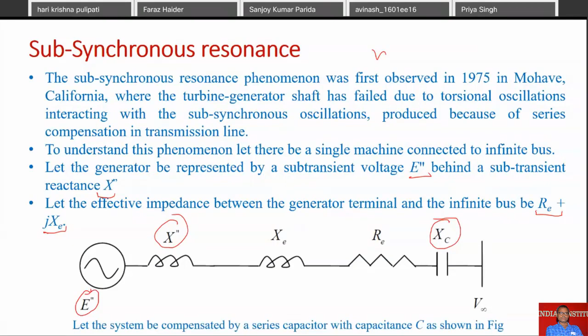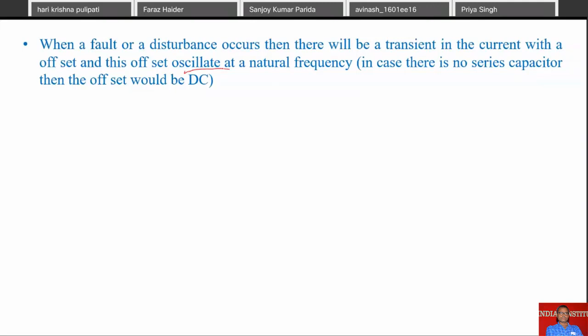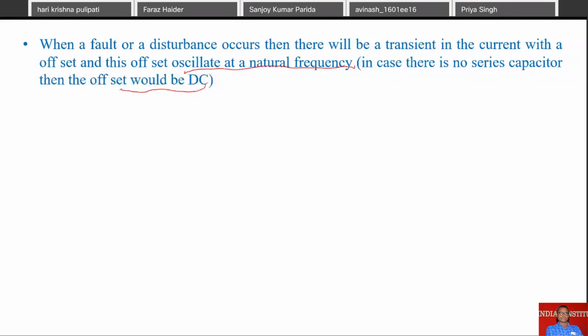Now let us analyze this. What happens when a fault occurs in a system? When the fault occurs, there will be a transient in the current with offset, and generally this offset oscillates at a natural frequency. If the capacitance is not present, there is no natural frequency, so it is called DC offset. But as soon as the capacitor comes into the picture, it has a natural frequency. This fault current, the DC offset, is decaying in nature, but it is oscillating at a natural frequency. It is nothing but 1 by root over LT C, where LT is the total inductance and C is the series compensation capacitance.